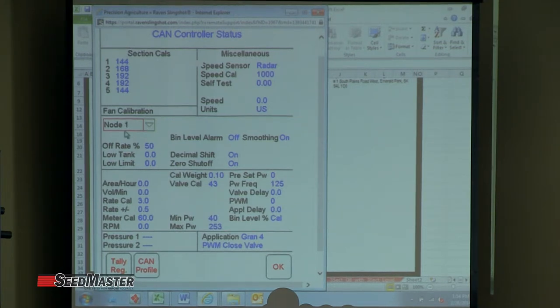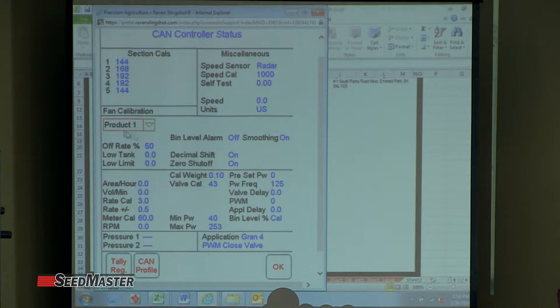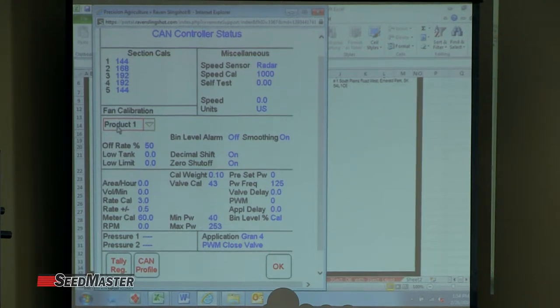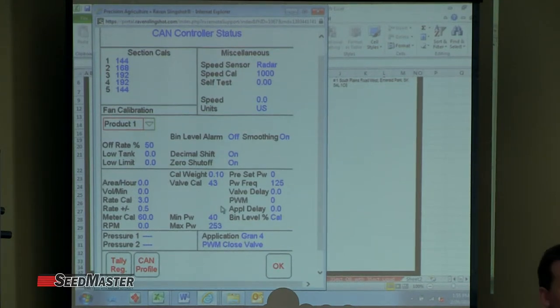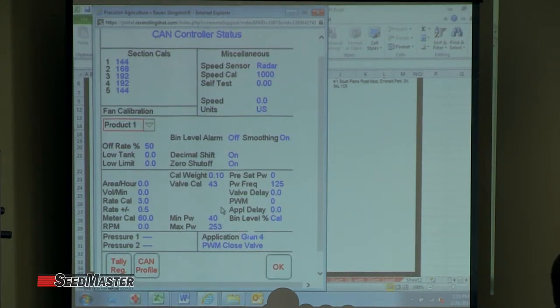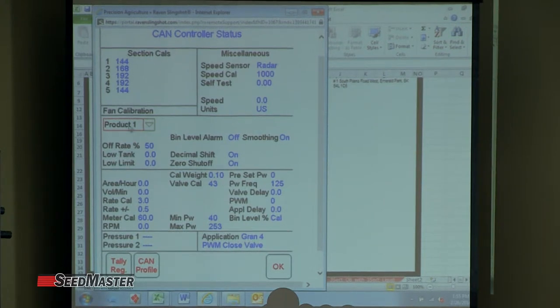Below that, it shows up product one, node one. Each product one or node one has boxes in here — valve cal, meter cal, all that — and your application type. These three boxes are settings specific to that product, that meter, or the bin. When you make a change to the cal weight in here, it's changing it for whatever product is displayed.